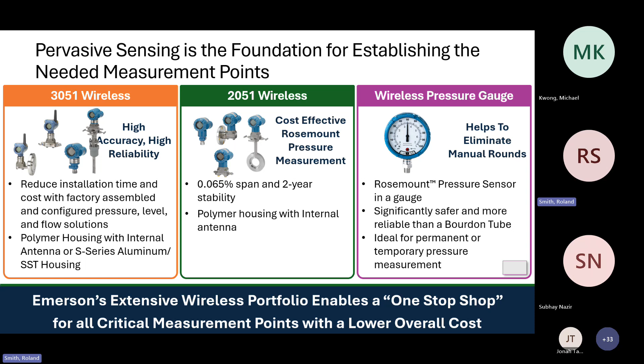So this is a neat product where we're replacing mechanical type gauges, Bourdon springs, in a mechanical gauge. So when a mechanical gauge gets overpressured, it will never return to the same spot. It basically becomes inaccurate and gets thrown away. The other thing that happens with mechanical Bourdon springs is they get blown out. So there's a safety aspect. The burst pressure of the Bourdon spring has been violated, and liquid process or gas process can be emitted from that gauge itself. So this wireless pressure gauge takes care of a lot of those process and safety application concerns away because it's got a pressure module in there.